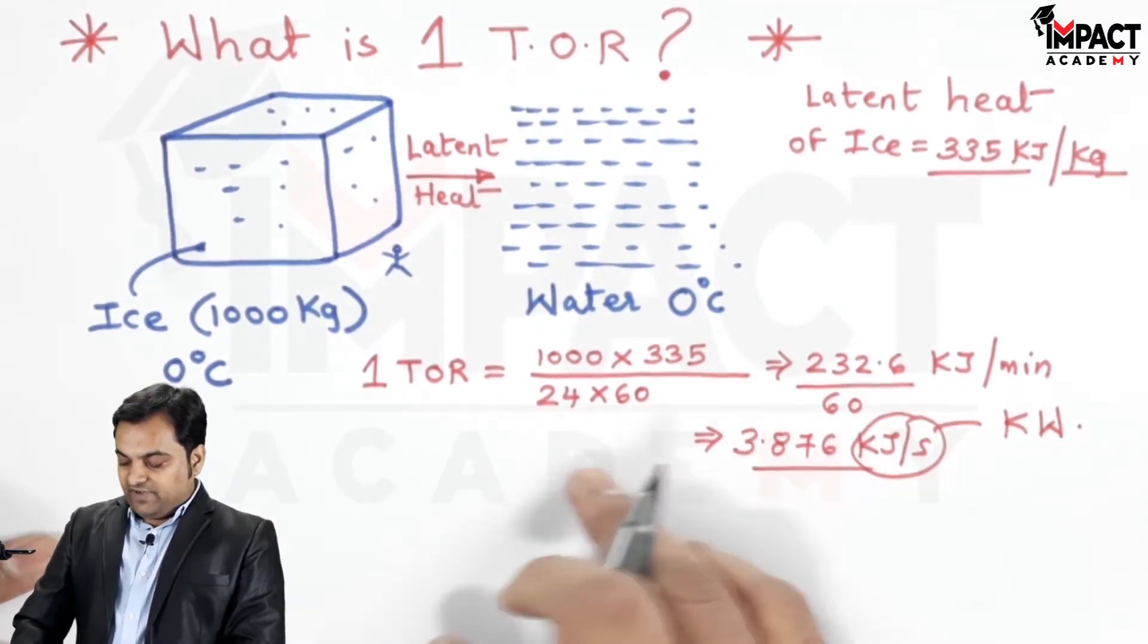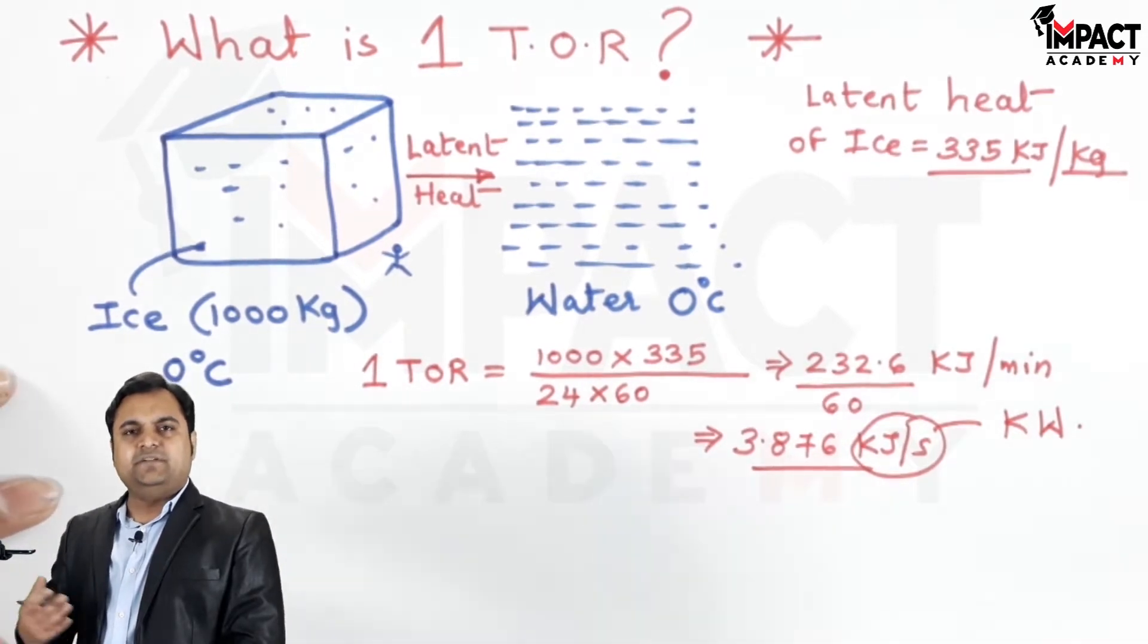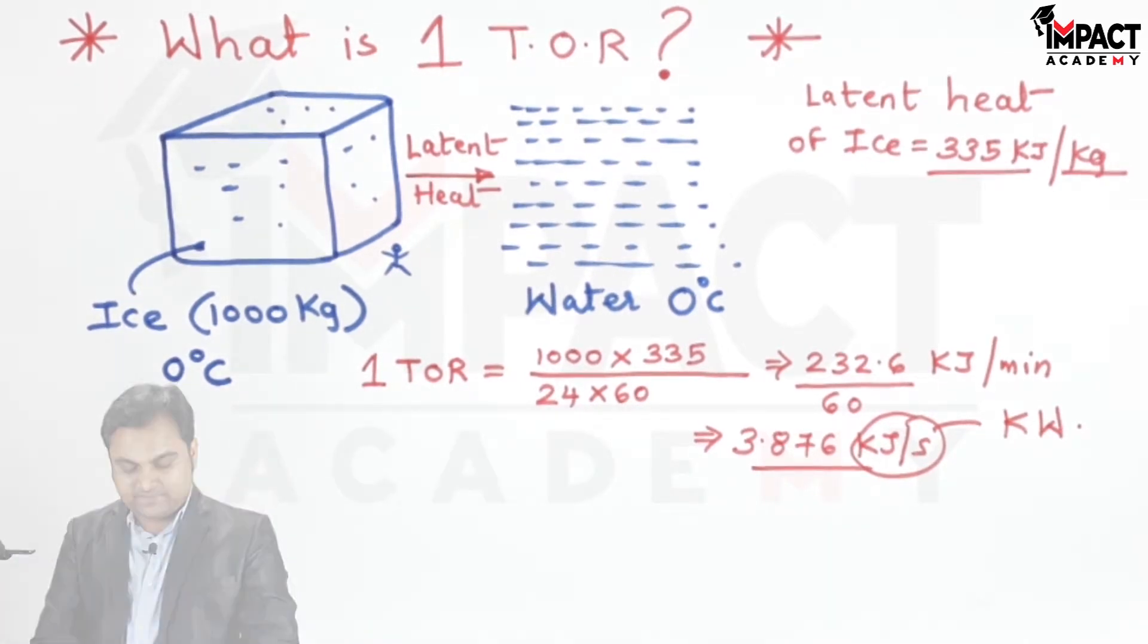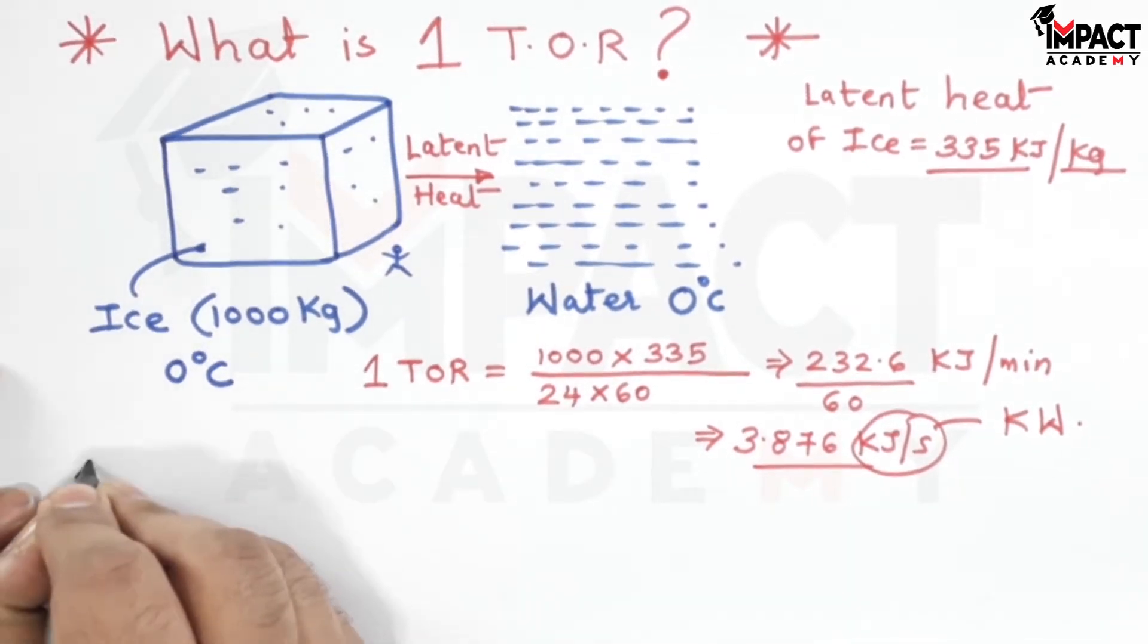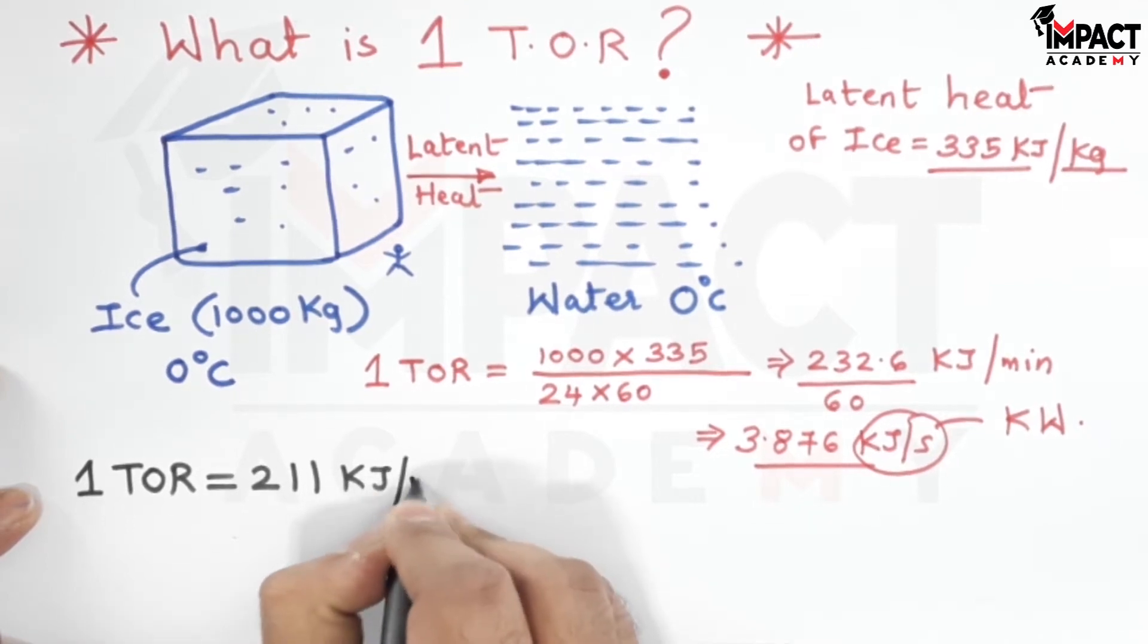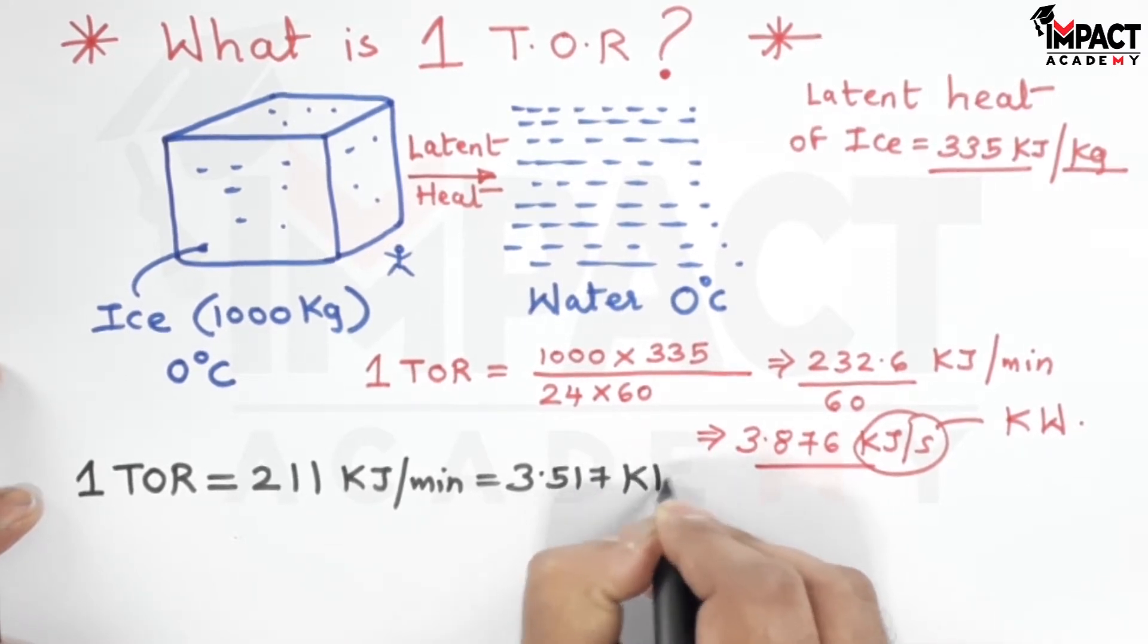Now these are the values which I'm getting, but with the help of some experiments and practical readings, one ton of refrigeration is taken as 211 kilojoules per minute, and it is equivalent to 3.517 kilowatts.